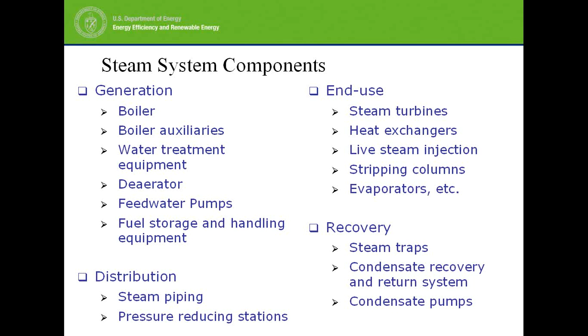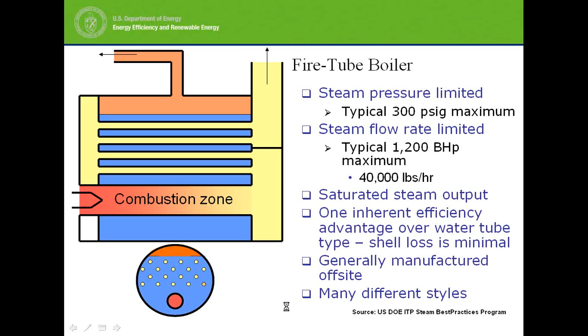When we get into the generation area, we start off at the boilers. Most of you will probably have seen fire tube boilers. They typically have some pressure limitations and some steam flow limitations. These are classic bread and butter for low pressure, for small to medium steam users. And yes, there is an overlap. Generally, they create saturated steam. They are manufactured off-site, so these are the package units, and many different styles are available.